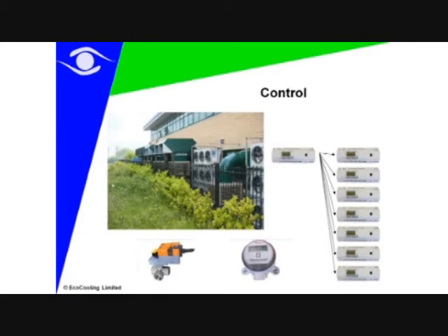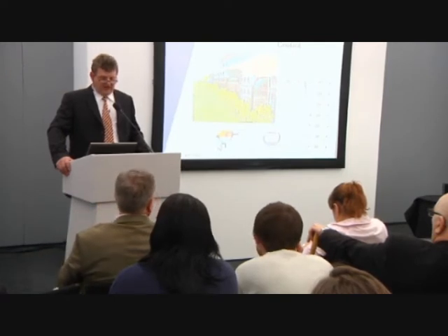Control is at the heart of all systems in the IT. Many ventilation systems are put in a very simple way and don't offer precise control or communication. In this system here at M247, we put these coolers in pairs — stacked pairs of coolers — and each cooler has its own PLC controller, which is then linked to a master controller.